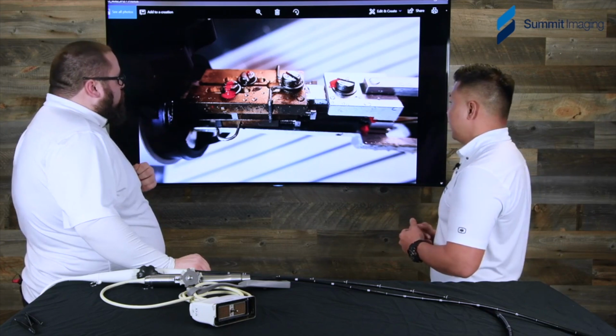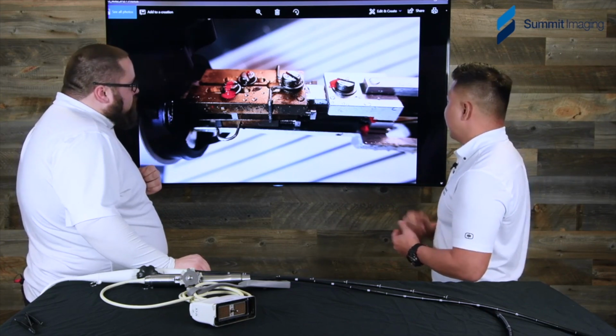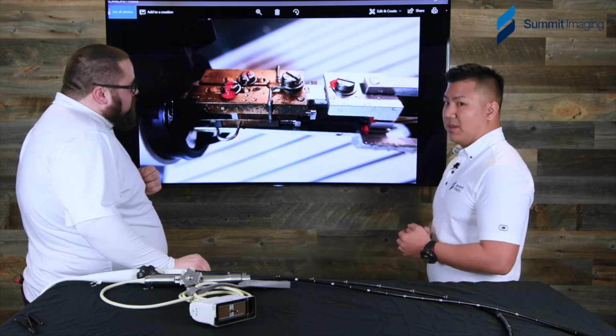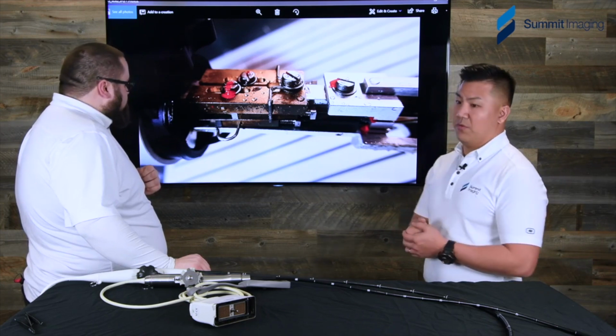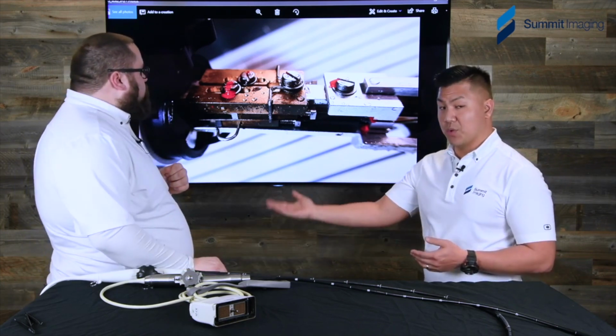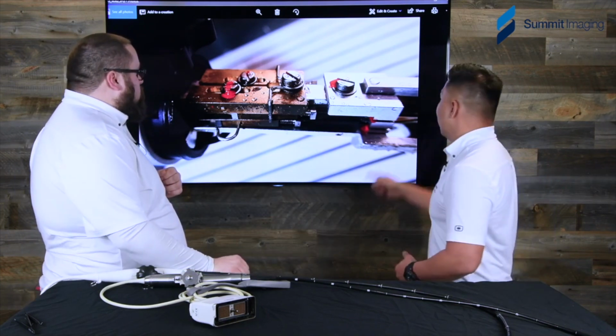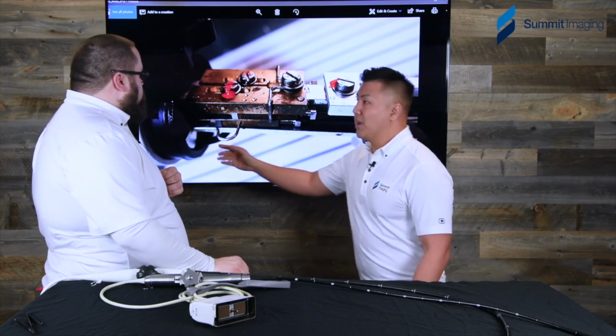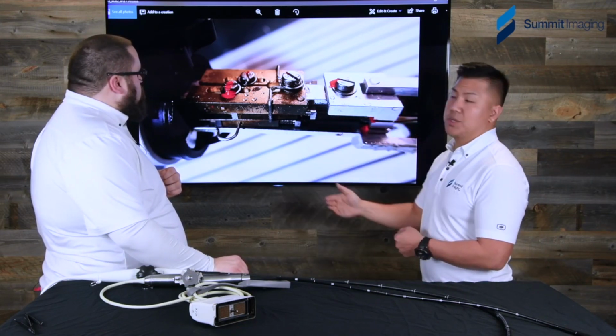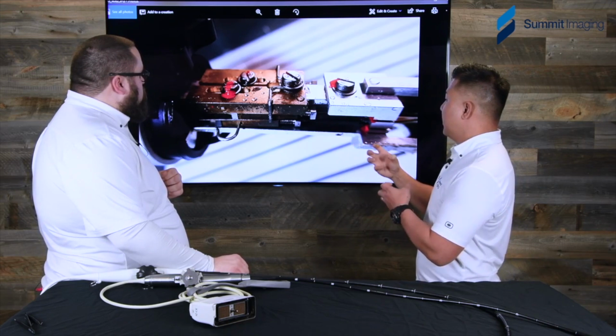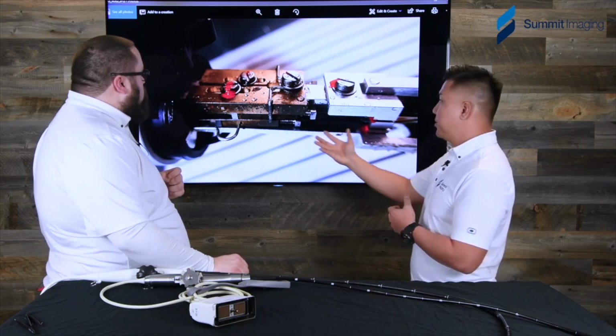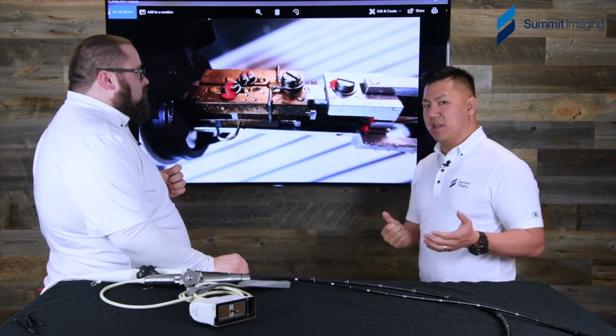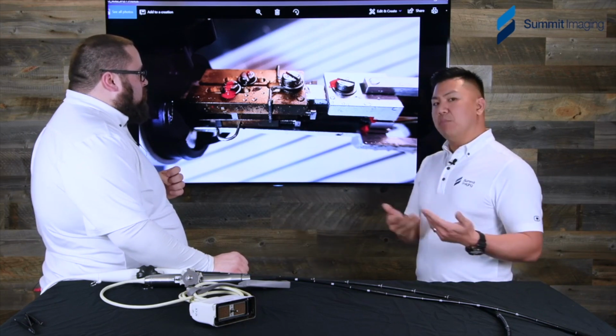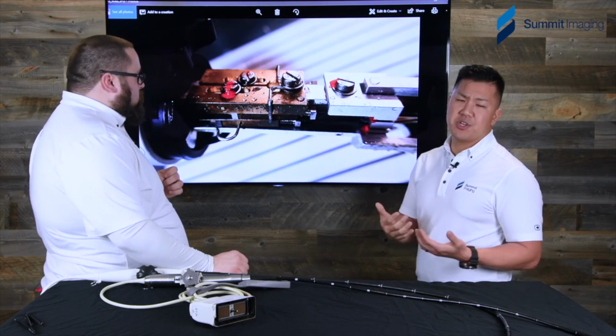see is that there is the bundle of the electrical lines that go from the connector that goes to the ultrasound machine all the way to the crystal. That's underneath. And so not only are the mechanicals of the articulation lines exposed to this fluid, so are the electrical lines. Luckily, they're wrapped up pretty good, so there's typically not too much damage there.